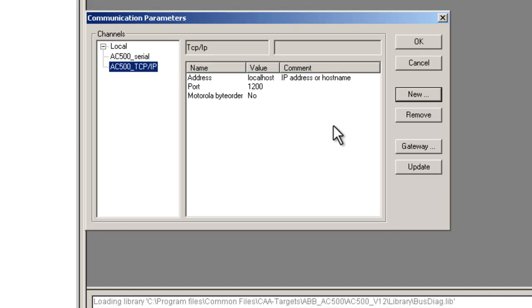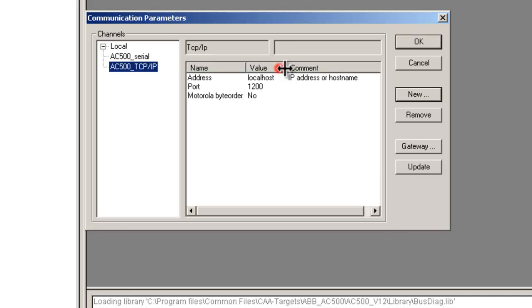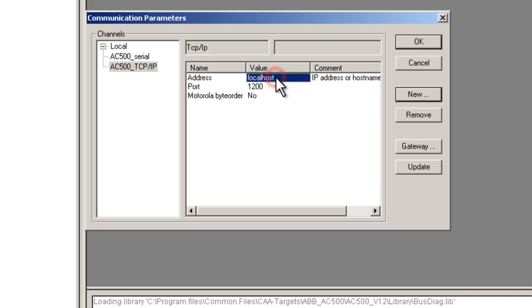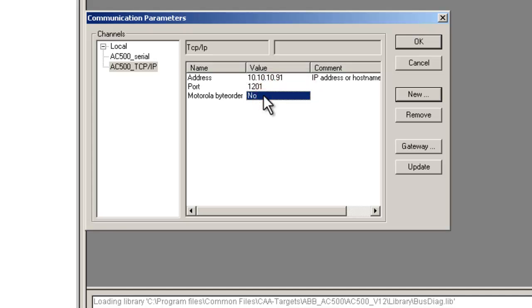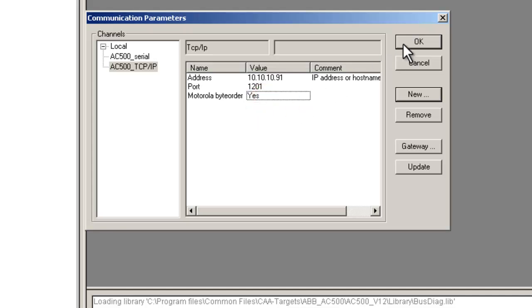Now, we define the parameters. Double click the value field and write down the CPU address. The port number is always to be 1201. The Motorola byte order value has to be Yes. After clicking on OK button, the connection parameters are set.